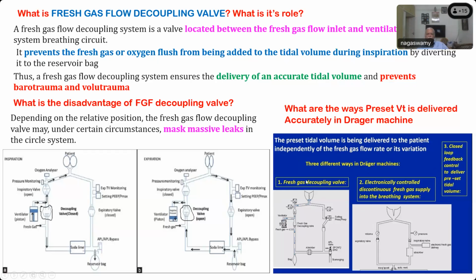So in the Draeger, it is fresh gas decoupling. Other machines use electronically controlled discontinuous fresh gas supply. And some machines use what is called closed loop feedback control, where any excessive gas will be vented out. Only the set tidal volume will be delivered to the patient.